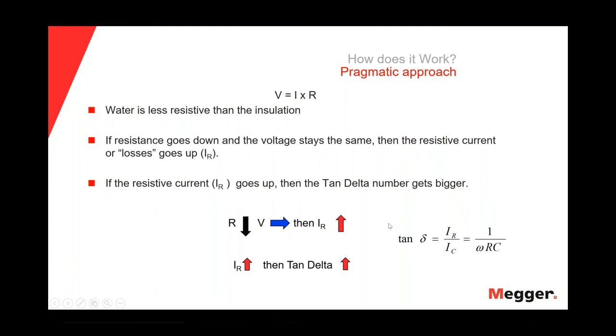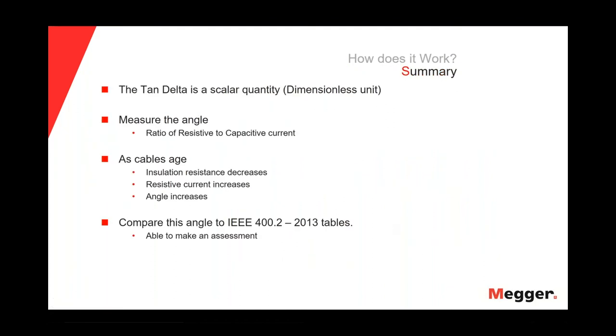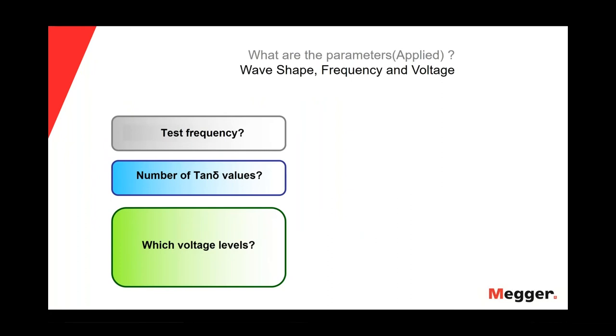So, doing a summary of how the tan delta works, we can say that the tan delta is a scalar quantity, a dimensionless unit. We measure the angle of the ratio of the resistive to the capacitive current. As the cable ages, the insulation resistance decreases, the resistive current increases, and the angle increases. And of course, we can compare this angle to the IEEE 400.2, and we will be able to make an assessment and a decision.